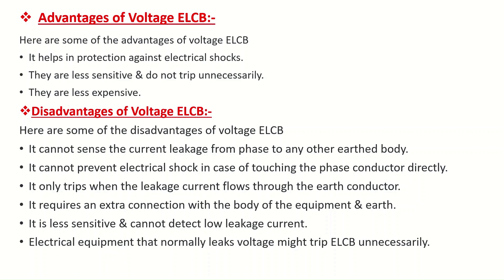Disadvantages of Voltage ELCB: It cannot sense current leakage from phase to any other earth body. It cannot prevent electrical shock in case of directly touching the phase conductor. It only trips when the leakage current flows through the earth conductor. It requires an extra connection with the body of the equipment and earth. It is less sensitive and cannot detect low leakage current. Electrical equipment that normally leaks voltage might trip the ELCB unnecessarily.